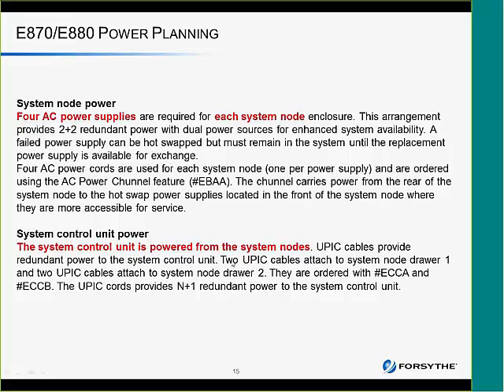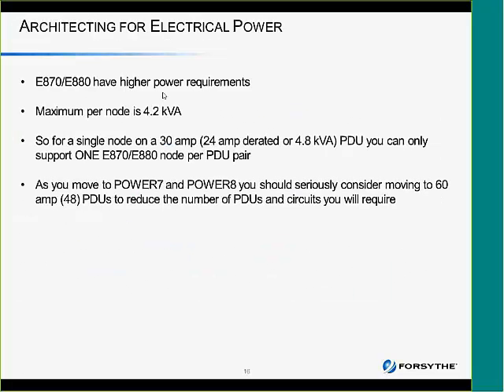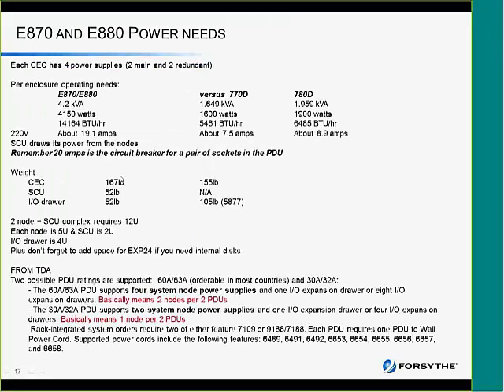The actual system control unit is powered from the system node, so it does not need its own power supply. The only time you need to provide power for the system control unit is if you add the DVD. And if you add the DVD, there's a couple of special power cords that we add. But that's very, very minimal relative to the 4.2 amps that the actual 870, 880 pull. So this is one of the reasons we're having the conversation, is that with Power 8 becoming so incredibly powerful, it's drawing more power, and we need to be able to plan for that. And this is basically reiterating what I just said, that with the E870, 880, and even the S824 requiring more power, because the S824 is around 11 amps per server, we really need to start considering going to the larger PDUs. Well, actually, the larger line cords.